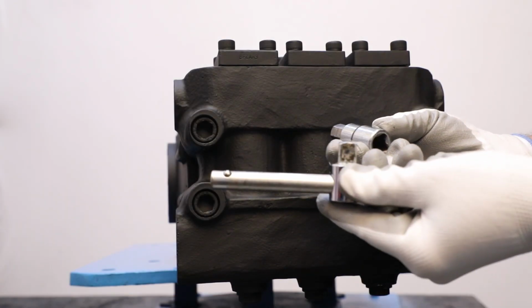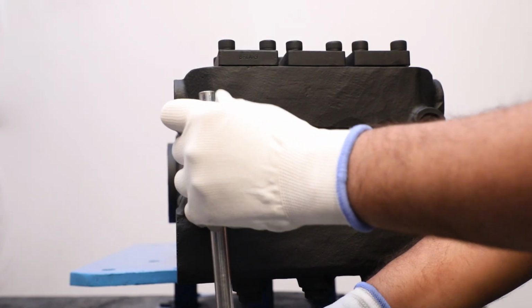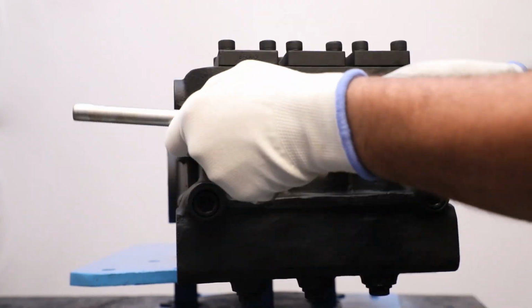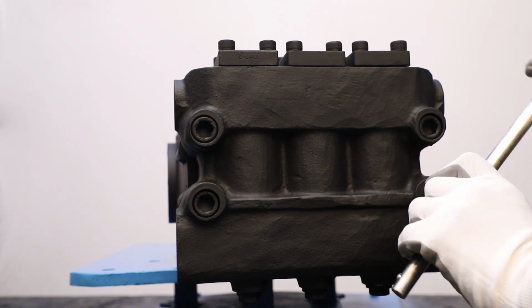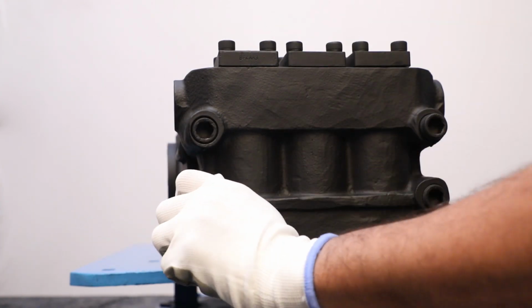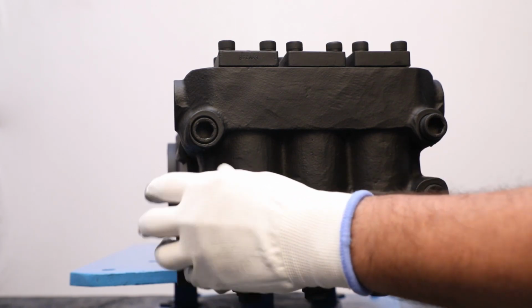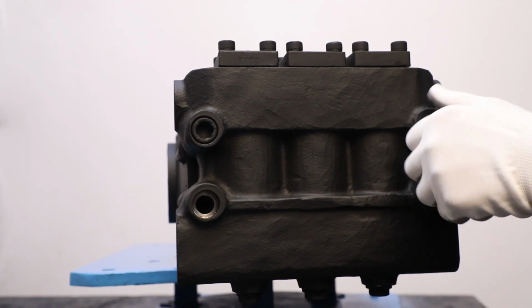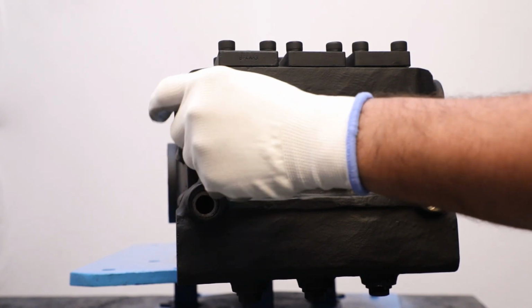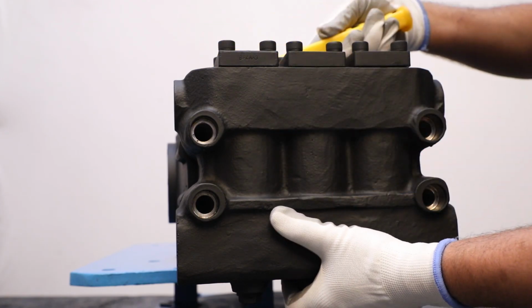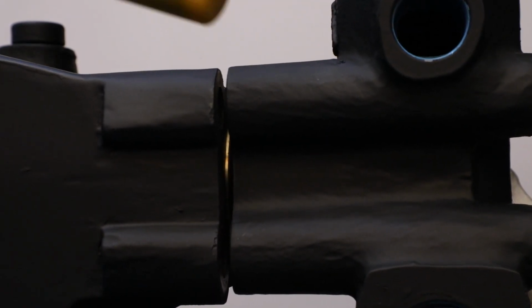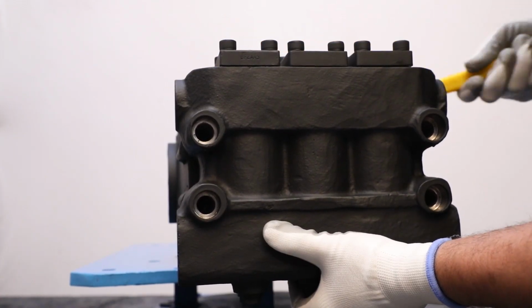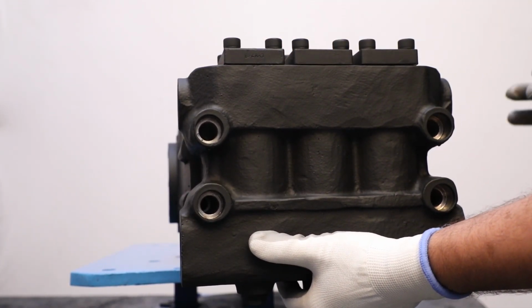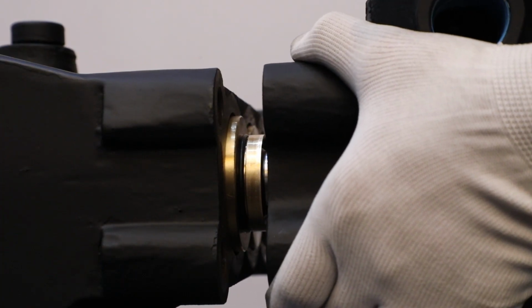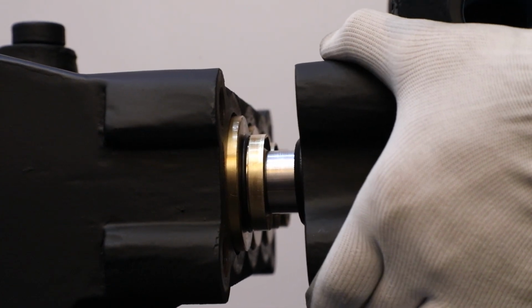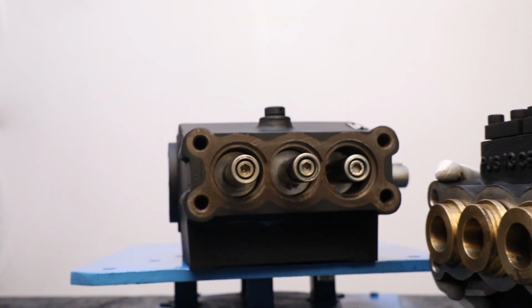Take Allen key socket and wrench and remove 4 M16 by 150 cap screws in a diagonal manner. After that, take rubber hammer and gently push pump head to separate it from crankcase. Then, manually pull out the pump head carefully because of its heavy weight and put it on the clear surface.